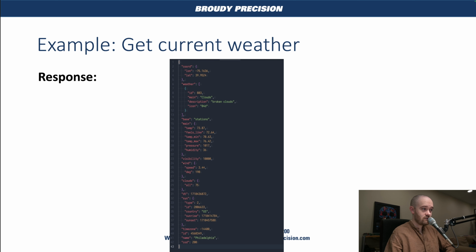So now this is what our response looks like. We're going to get this piece of JSON, and it's giving us a whole bunch of structured information. And then from within Niagara, we can make our way down this information and pull out specific parts. Okay, hey, I actually just care about the temperature. The temperature is always going to come in this format. So that means that I can just pull in temp, and there's my temperature. I could throw it into the JSON toolkit. It will spit out that value, and then I can add facets to it and then use it exactly as I would expect to in Niagara.